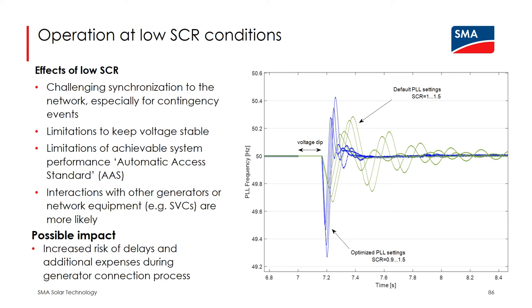So when talking about low SCR, it is quite important to understand that SCR does not give you a complete picture of what one can expect. It's just a good indicator of how challenging it may become to find a good tuning of the overall generator. One of the most critical points typically is the synchronization of an asynchronous generator to the existing network. On the right-hand side, you can see the inverter internal frequency, which is the value coming out of the PLL, a part of the inverter control software which synchronizes the inverter to the network.